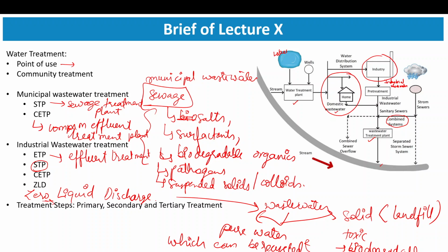So all sorts of secondary treatment can be provided. And lastly, whatever is not treated by any primary or secondary treatment, in that case we provide tertiary treatment, which is a specific treatment procedure. It can include adsorption, membrane filtration. It can also include disinfection and advanced oxidation process for all the non-biodegradables and so on.